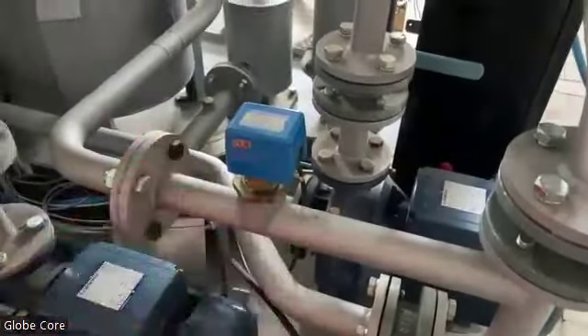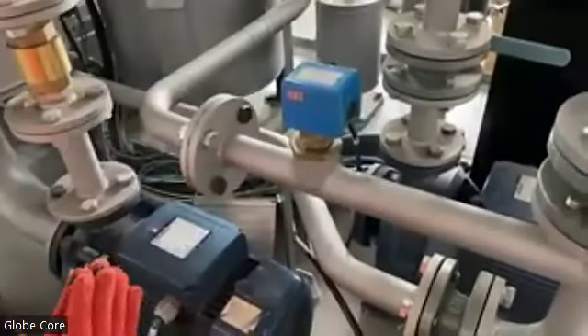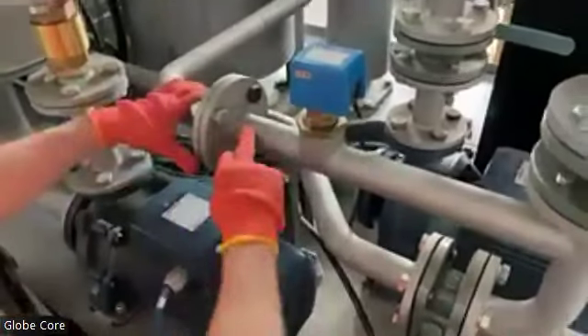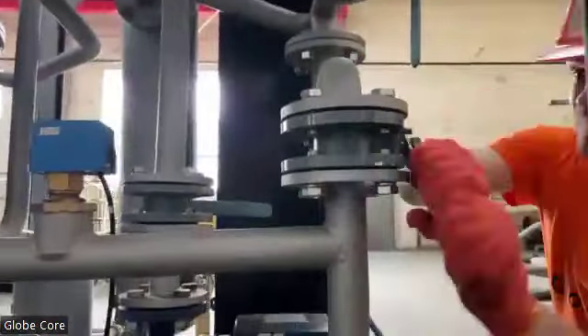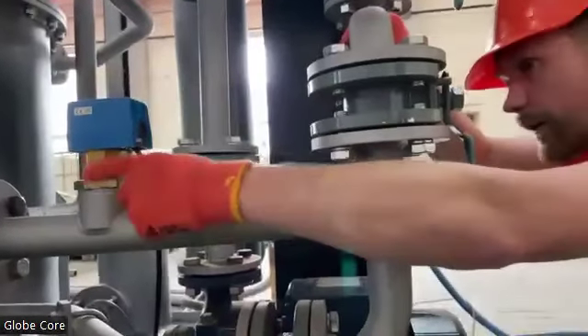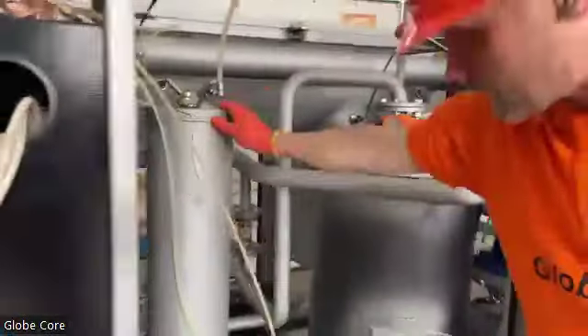So this sensor detects the presence of the flow and controls the operation of the heater. When there is no oil, operation of the heater is interlocked. Then here we can see the split point for the flow. First one is for the heating and filtration mode. This valve is closed. This one is open. So oil goes after the first fine filter, after the heater, through the flow sensor, to the second fine filter. It's over there. So oil comes here and finally goes out. So this line is used when we work in heating and filtration mode.